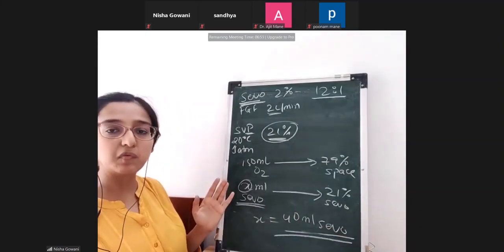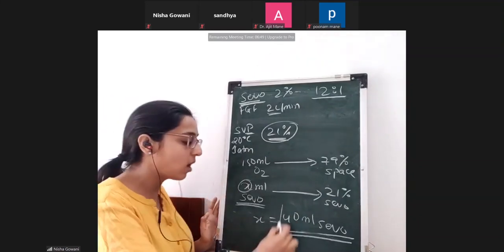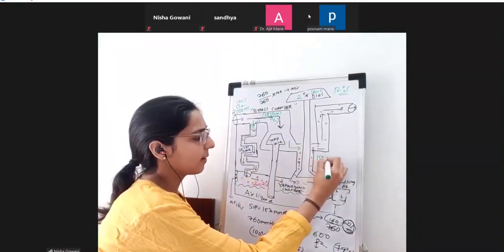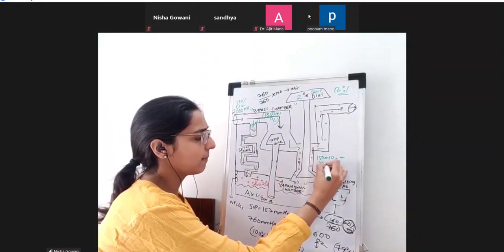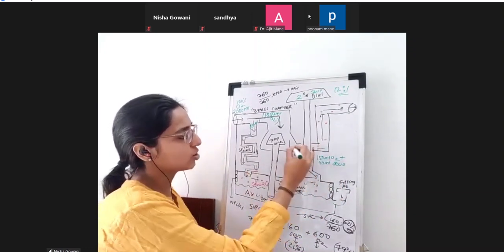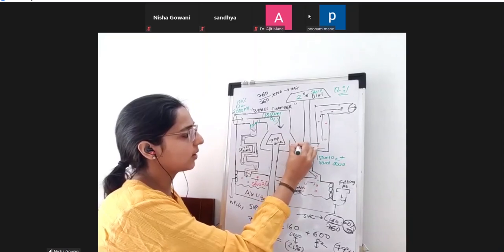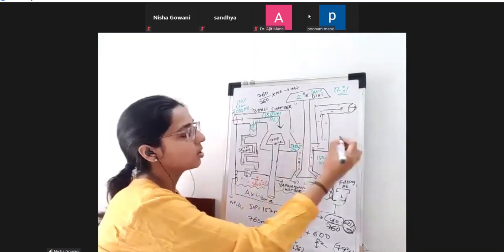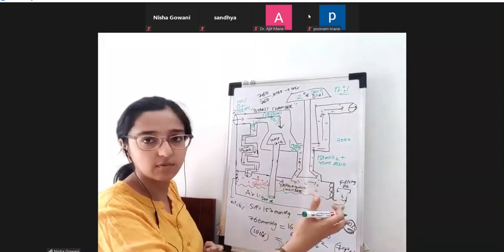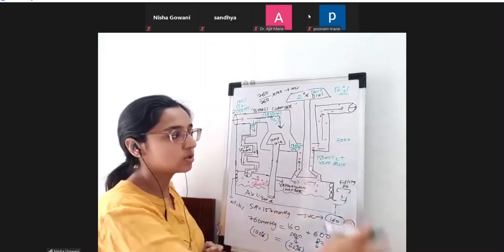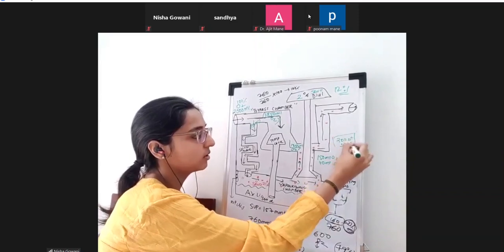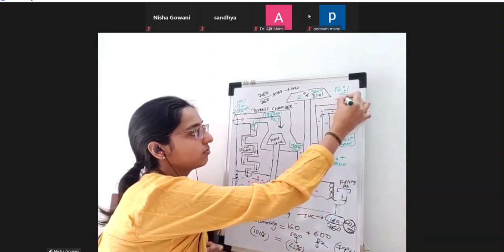This 150 ml of oxygen, which is going through the vaporizing chamber, will now pick up 40 ml of sevo. It is 150 ml oxygen plus 40 ml sevoflurane going up. It has joined with 1850 ml oxygen. My incoming oxygen was 2000, right? My outgoing oxygen also will be 2000. I'm not going to lose oxygen somewhere here. So this outgoing oxygen is 2000, plus I have 40 ml of sevo, which has joined my oxygen. So my total output is how much? 2040 ml.